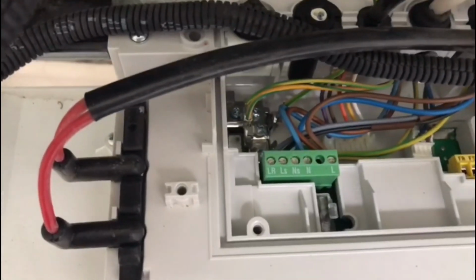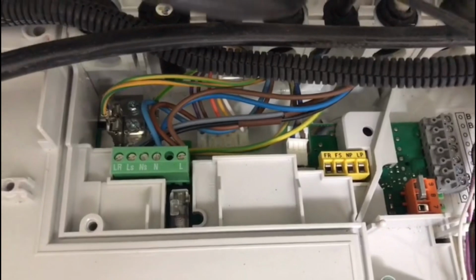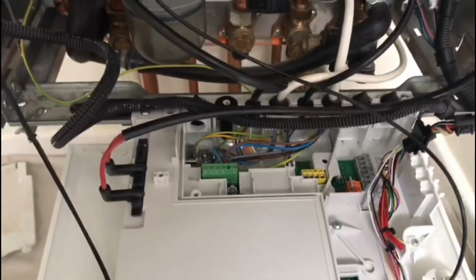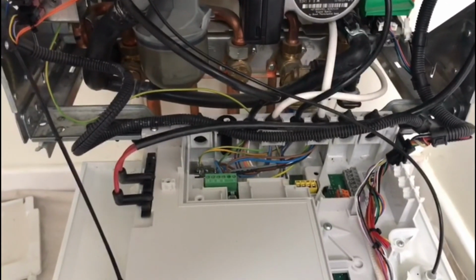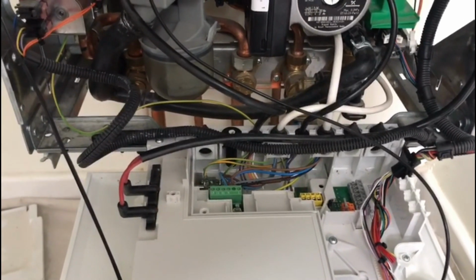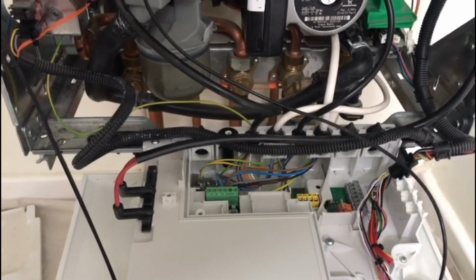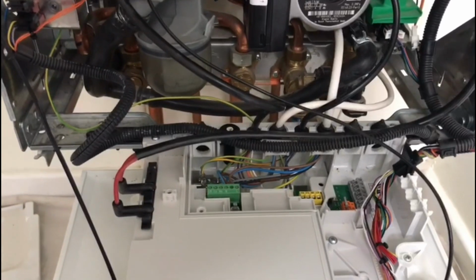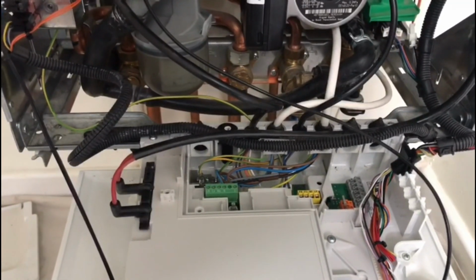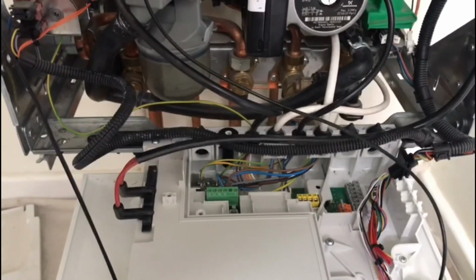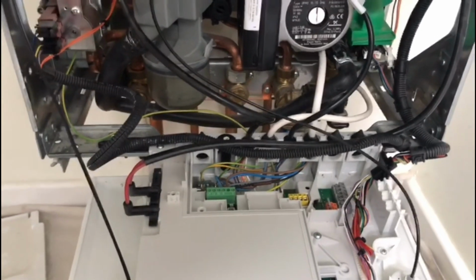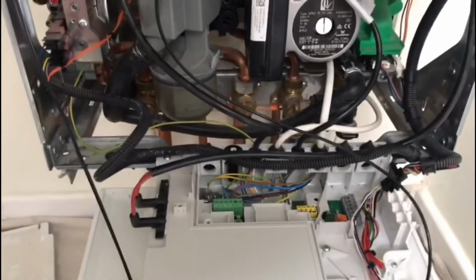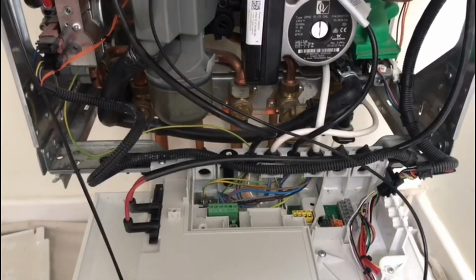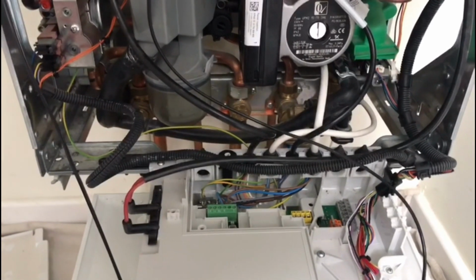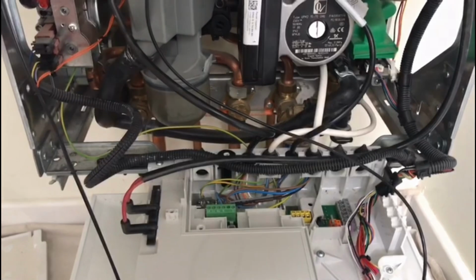Now to do your checks on this boiler, there's 4 checks you have to do. The first one is an earth continuity test. Second is a short circuit test. Thirdly is a resistance to earth test. And the fourth one, which is a live test, is a polarity check. I'll show you how to do the dead tests first, the first 3. It's quite simple, not too daunting, and it'll tell you a lot of things before you can proceed with work. But these are the proper electrical checks you should do on a boiler.